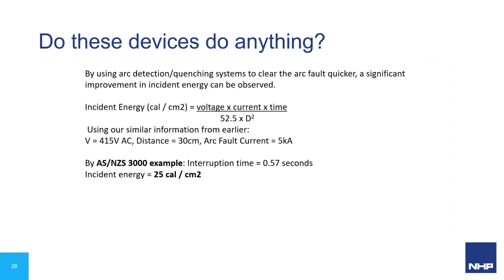An important question we field quite regularly is, do these things actually do anything? There are always products out there in the market. What's the actual effectiveness of these things? So let's go back to that example we had from AS3000, with the interruption time of 0.57 seconds. Plugging those numbers into the formula we had earlier, we get 25 calories per centimeter squared. At that level, you're definitely looking at a spacesuit. It's a pretty intensive setup that you're talking about there.